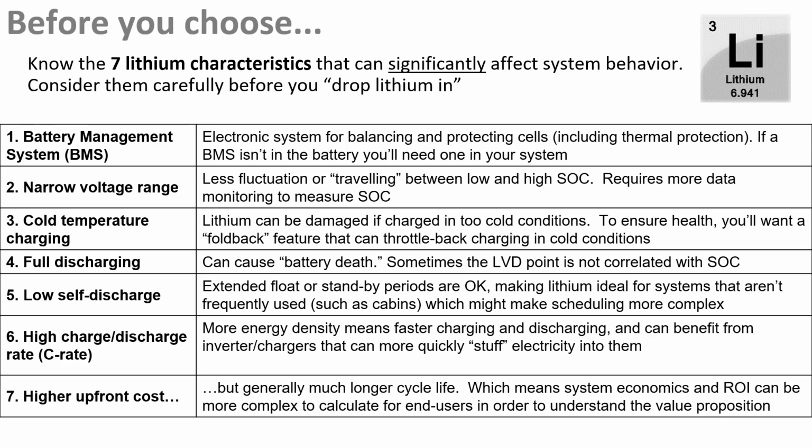One of the really big benefits of the high charge and discharge rate of lithium is that you can take into account a faster charge rating. I've seen many systems where we're looking at our 60 amp controller, and we may have to actually decrease the charge rate because there's a lot of power coming into the batteries. And if you don't have the largest bank with lead acid, you often will have to dial back that charge rate so that you don't exceed, maybe, no more than a quarter of its amp hour capacity. And even that's on the high side. You can definitely open the throttle when it comes to charging with a lot of lithium systems. So you want to make sure to take advantage of that extra power.